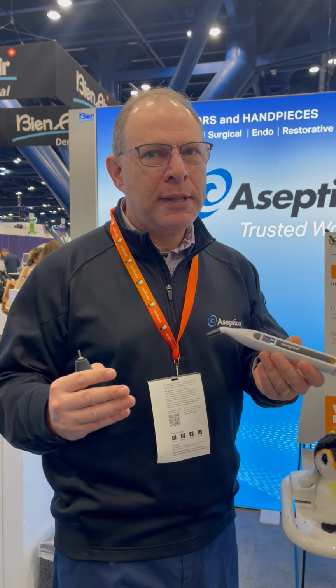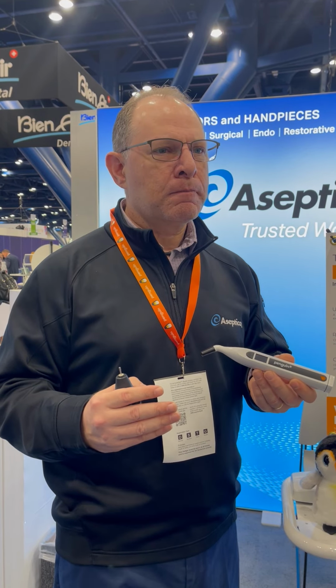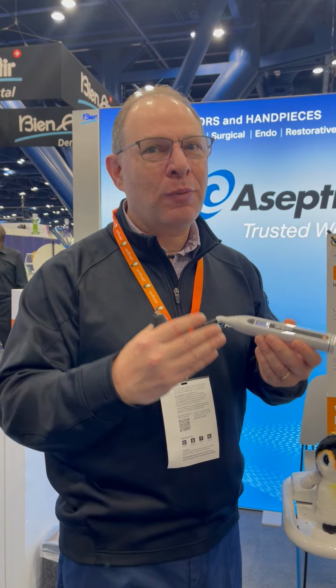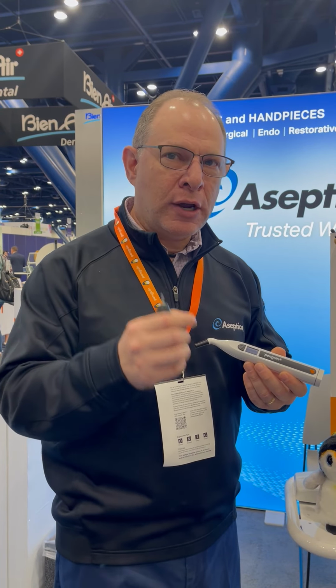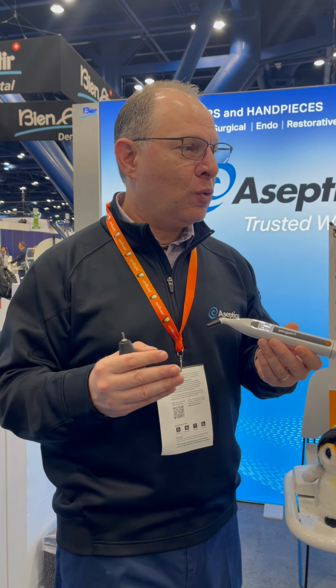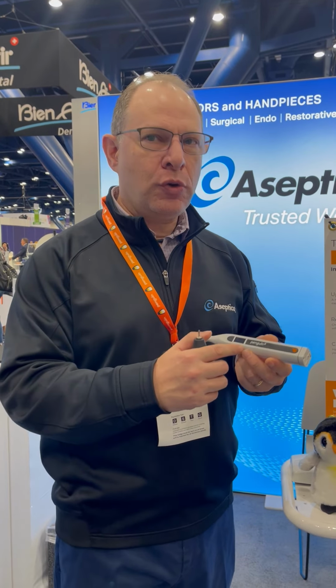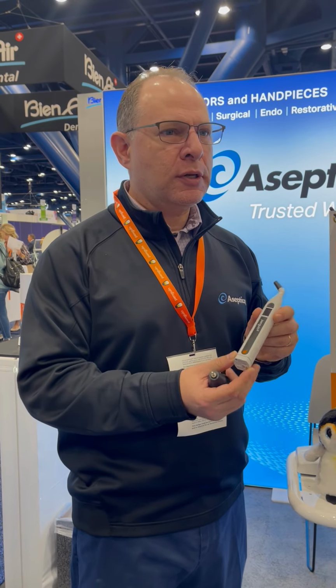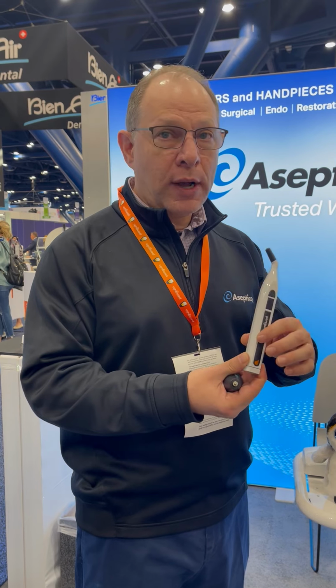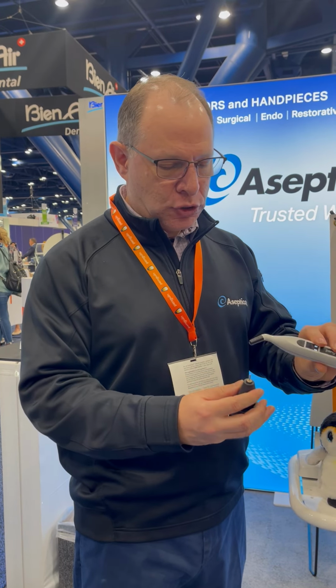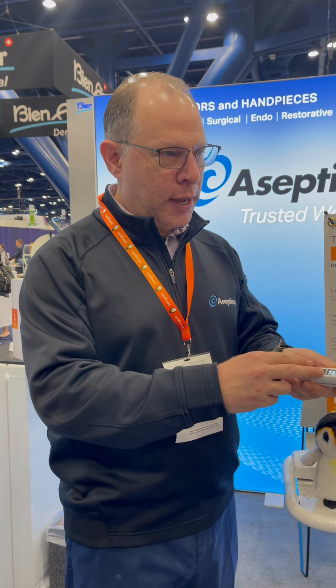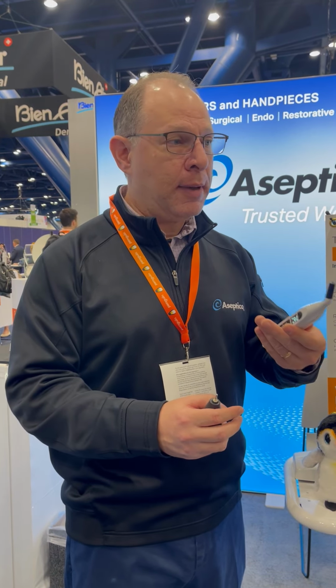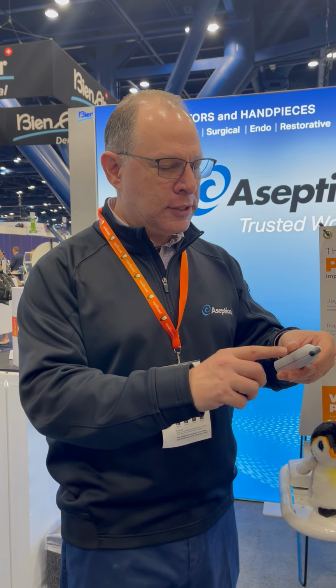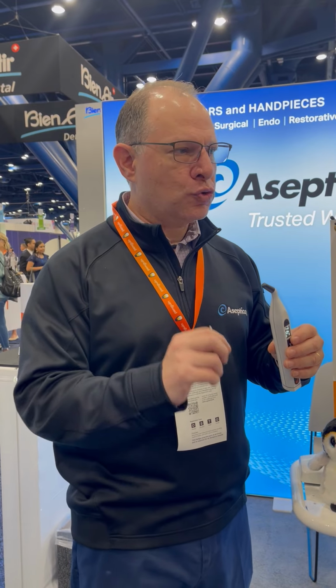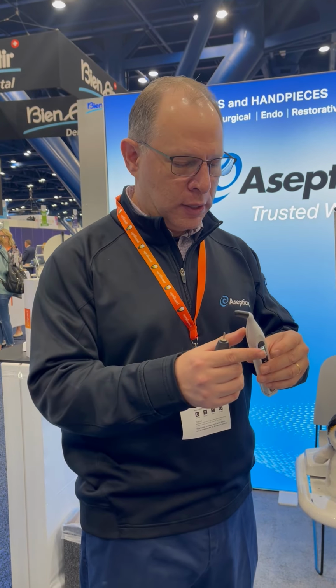If you have a very low ISQ number and 4 months down the road it's still low, that implant may not be successful. But it's certainly a much more scientifically quantitative way to help determine when to restore the implant than using a mirror to tap the implant and say, oh, it sounds solid. Well, that's nothing you can write in a patient file, where with the ISQ number, you certainly can. And with the Penguin 2, some of the design refinements include rubberized grips and an upgraded display, so it's easier to see. The nice thing about the Penguin is that you have displays on both sides, so depending on where you're measuring in the mouth, you don't have to do a whole lot of wrist gymnastics to see what that number is. We don't send any data to the cloud, you just write it in the patient file and you're done, and you can move on.